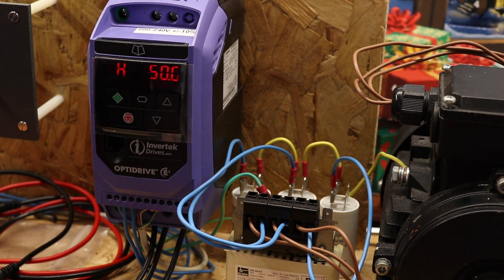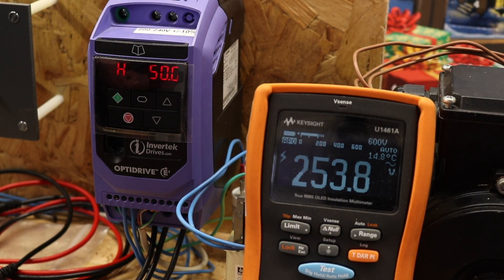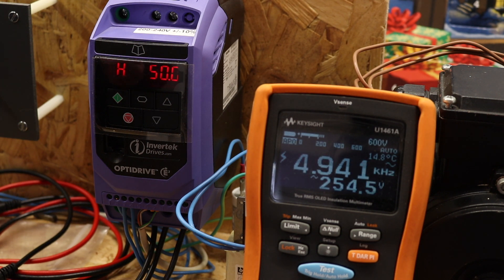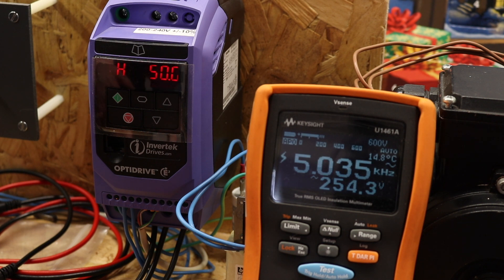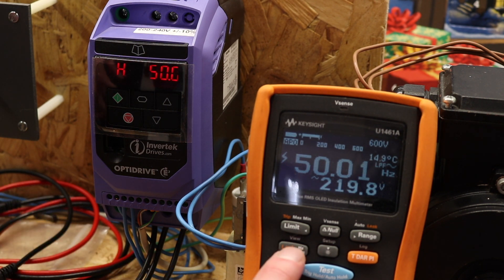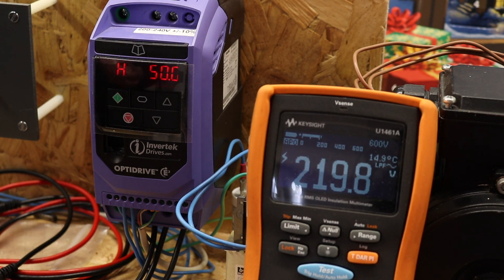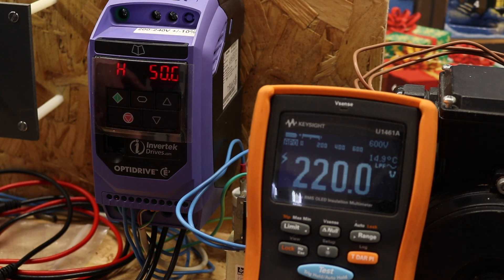The next meter we'll look at is the Keysight U1461A — its main competitor. You can see we are reading 253 volts, and going to Hz we've got 4.99 kHz, which is about a hundred times the nominal frequency coming out of this inverter. But this one has a low-pass filter. If I press low-pass filter, the frequency drops down to 49.99 Hz and the voltage reads 219.8 volts — totally stable, gives a good frequency measurement. Obviously this is also a pricey meter, not quite as much as the MTR-105 but getting very close.